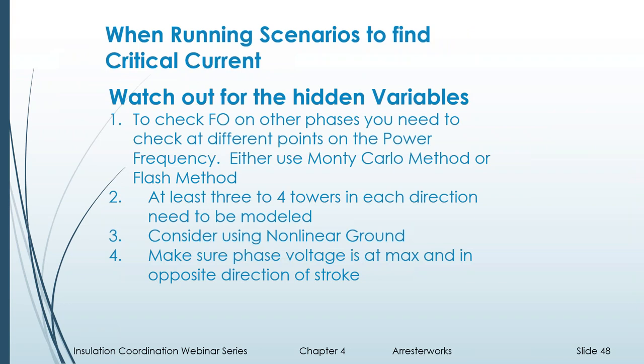Some of the things you need to watch out for: check for flashovers on other phases, and also keep your power frequency at the maximum, the peak voltage of the opposite polarity of the current stroke. Either you can use a Monte Carlo method, and there are different ways of doing Monte Carlos in ATP and other methods.